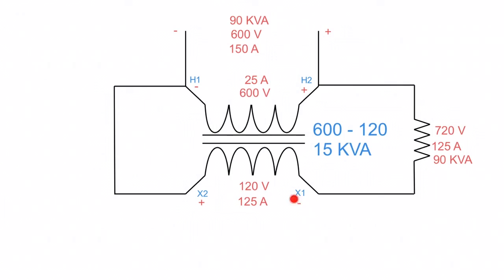The way this is connected is a boost connection. The mystery of the buck and boost connection auto transformer is solved — they're not that difficult. As with any transformer, you figure out your ratings, draw them in, determine line and primary polarity, which then determines secondary polarity. Then follow the circuit to see which way the voltages add or subtract, because the jumper puts the two windings in a series circuit. That is the buck boost auto transformer connection.